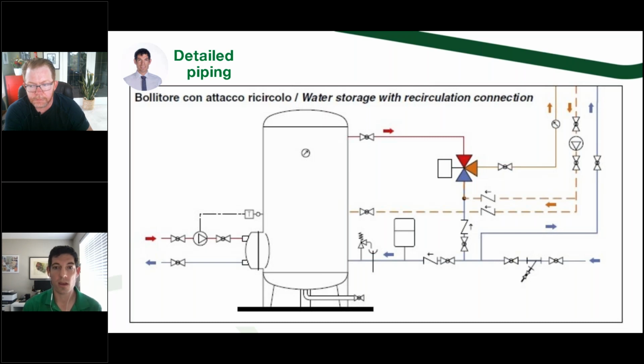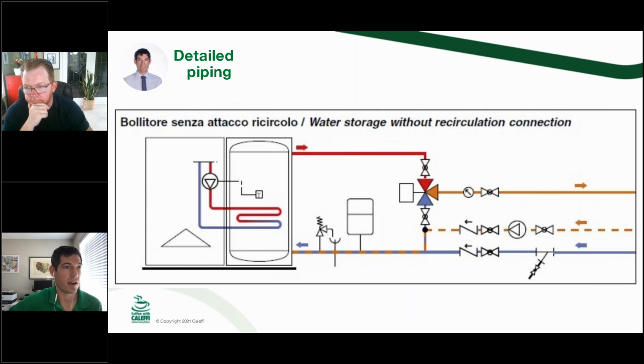So the first way that you can pipe it here, and you might have to help me out with the mouse on this one, is coming back to the Legio mix. In this case, we need to make sure that we're getting water back to the tank and then also to the cold inlet of the tank. With the Legio mix, it's going to have the ability to close 100% on hot. So this piping is one of the options with the recirc connection. So if you were going to pipe in a thermostatic mixing valve, that last one would be the way that you would go. And, I always get tangled up in these diagrams.